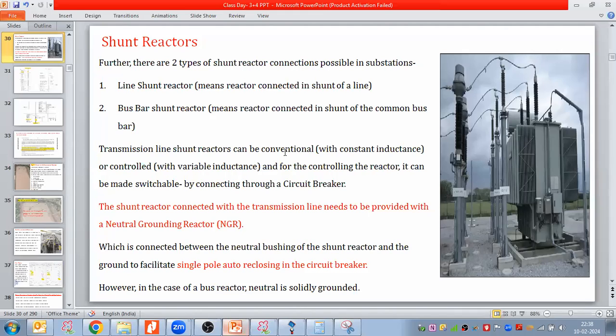As I told, it could be switchable or not switchable. So transmission line shunt reactor can be conventional with constant inductance, or controlled with variable inductance. For controlling the reactor, it can be made switchable by connecting through a dedicated circuit breaker. The shunt reactor connected with transmission...